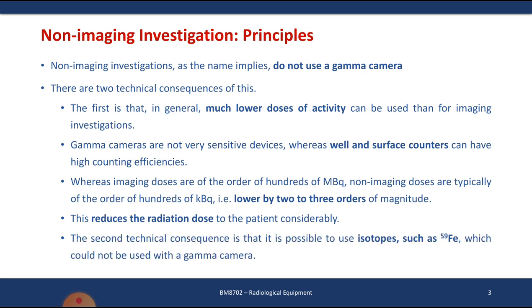In terms of dose magnitude, the gamma camera operates in megabecquerels — becquerel being the unit of radioactivity — whereas non-imaging techniques operate in kilobecquerels, which is two or three orders of magnitude lower. This significantly reduces radiation dose to the patient. Another advantage is that we can use different isotopes, such as Fe-59, which are not used in gamma camera imaging.